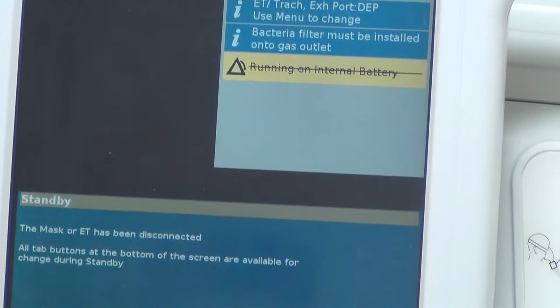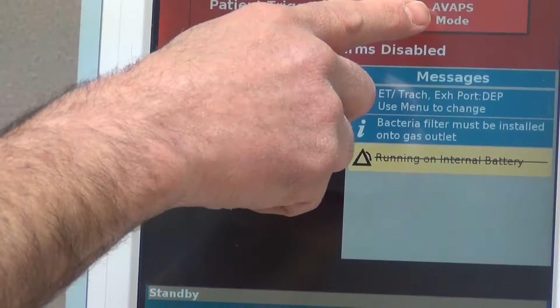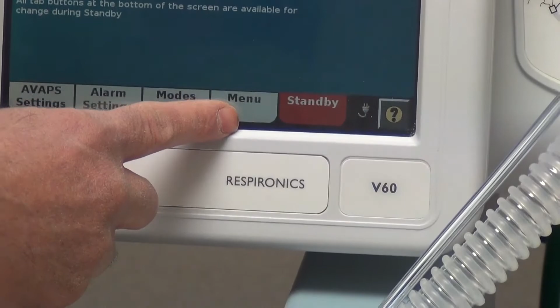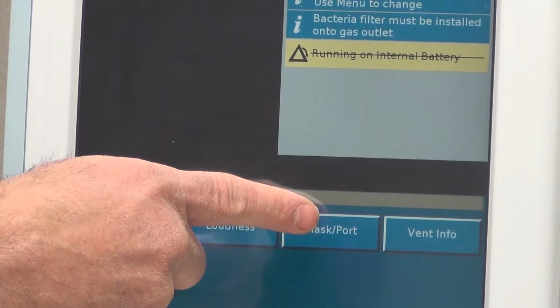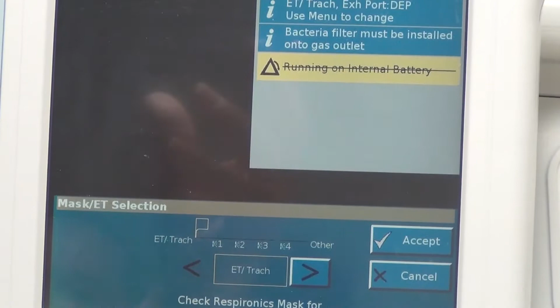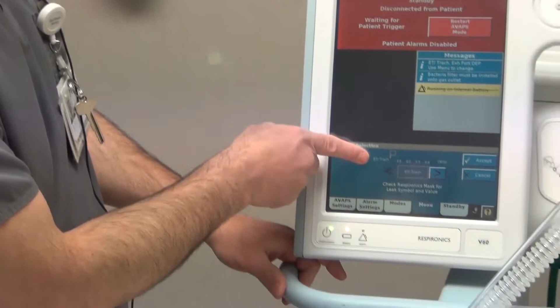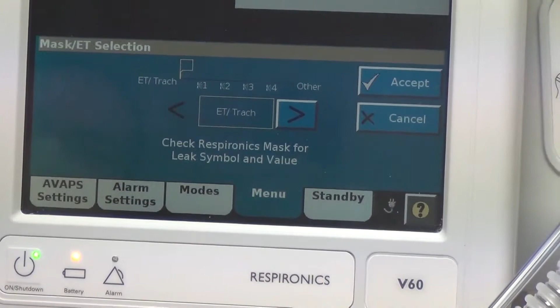To set this machine, we're going to follow these tabs here at the bottom. Notice that it says waiting for patient trigger or restart. Well, right now we're going to set the machine. So we're on standby. We're going to hit the menu tab and we're going to start with mask port. This determines whether we're using a mask or an ET tube, or what kind of mask we're using with the machine. For instance, right now it's set on ET tube trach, and I know that for sure because it's in this box right here.